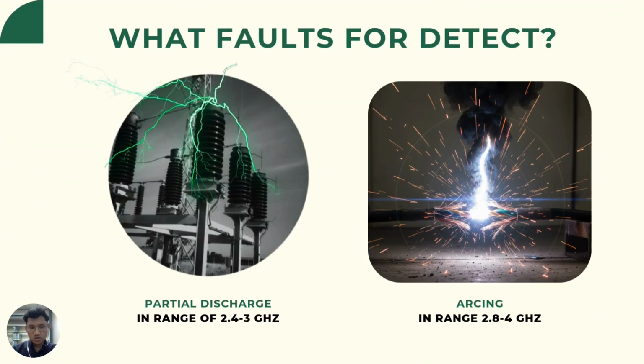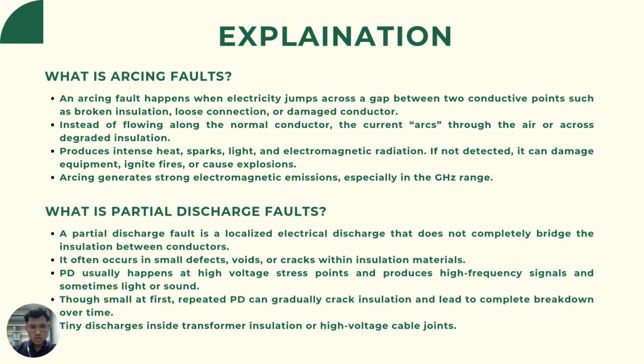So, what faults does it detect? Firstly, it will detect the partial discharge in the range of 2.4 to 3 GHz frequency, and then it will detect the arcing faults in the range of 2.8 to 4 GHz. This is the explanation of the faults.